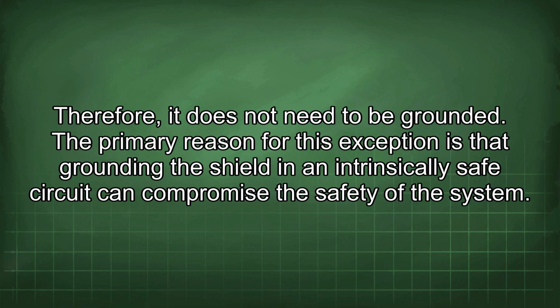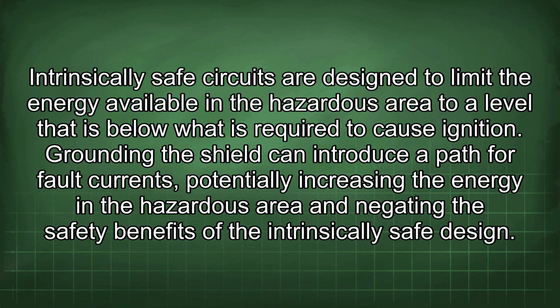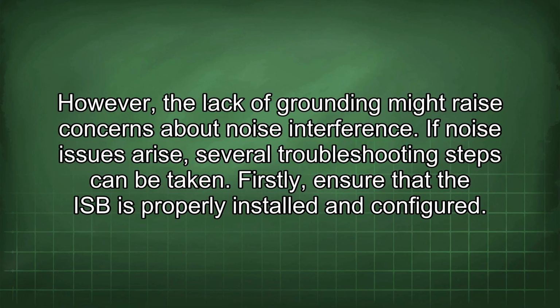The primary reason for this exception is that grounding the shield in an intrinsically safe circuit can compromise the safety of the system. Intrinsically safe circuits are designed to limit the energy available in the hazardous area to a level that is below what is required to cause ignition. Grounding the shield can introduce a path for fault currents, potentially increasing the energy in the hazardous area and negating the safety benefits of the intrinsically safe design. However, the lack of grounding might raise concerns about noise interference. If noise issues arise, several troubleshooting steps can be taken.